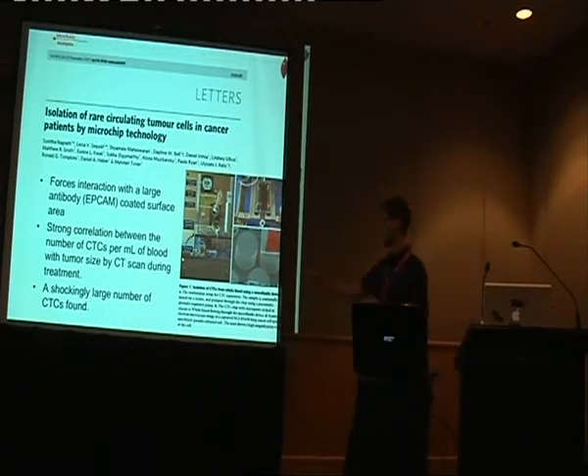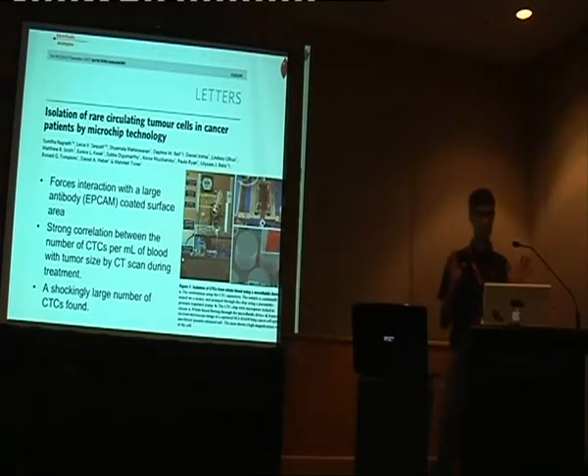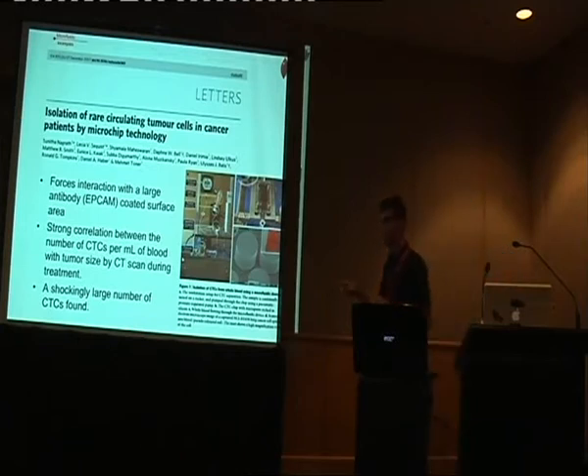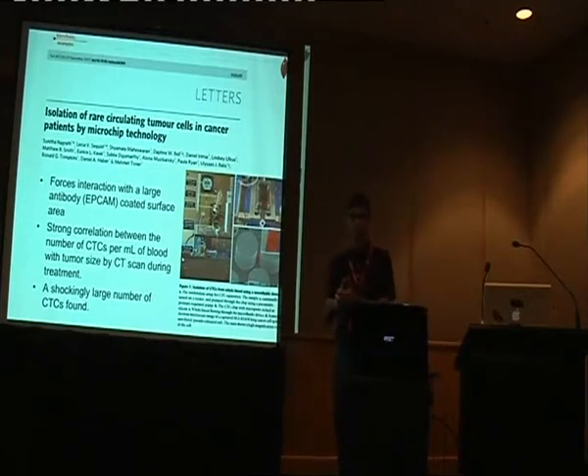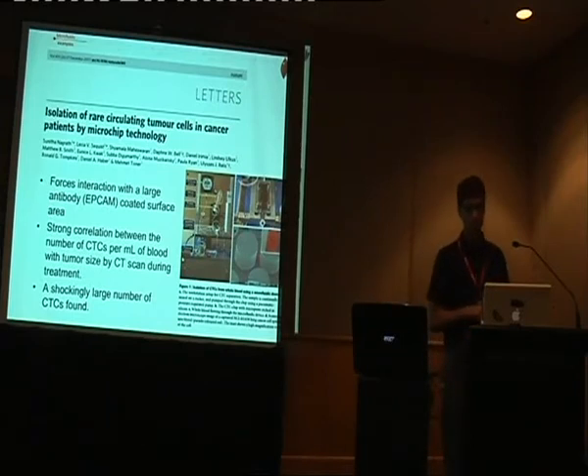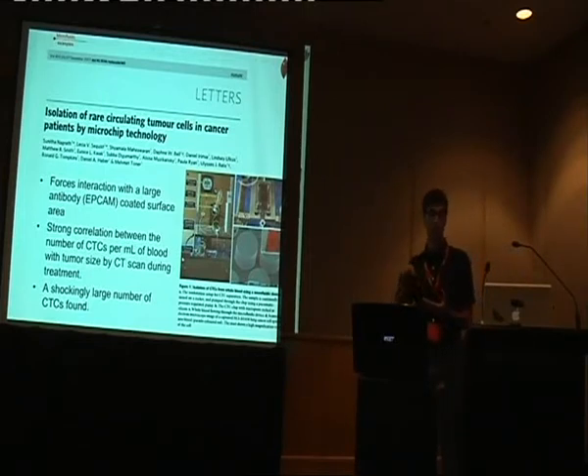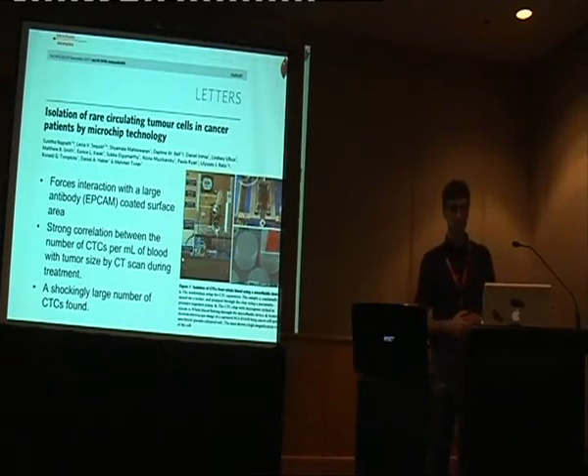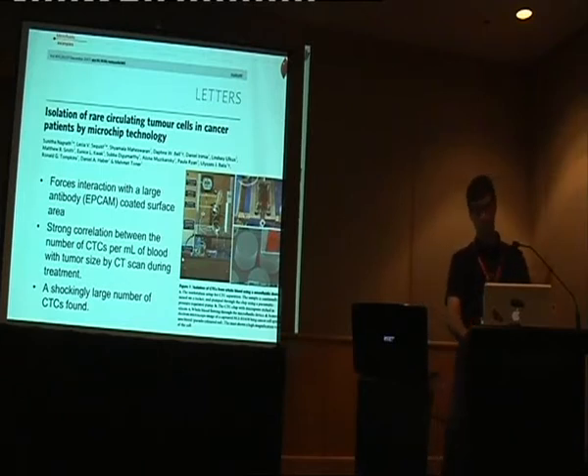The heart of the technology is some pillars — really simple stuff etched in silica and coated with an antibody, so it's classic smart surfaces. But the pillars create a huge amount of surface area interaction. As the cells go through, they're literally dragged across the surface of every pillar with a lot of surface area contact, which basically makes them stick better than on a normal capillary or parallel plate system. You can then take the lid off, do confocal microscopy, label the cells, and determine exactly what kind of cells were sticking there — removing nonspecific adhesion and so on.